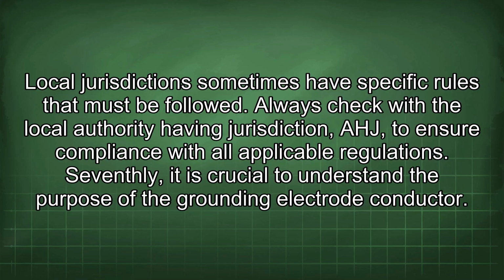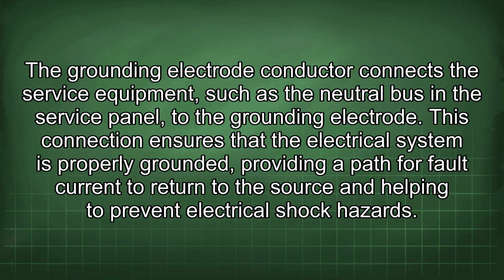Seventhly, it is crucial to understand the purpose of the grounding electrode conductor. The grounding electrode conductor connects the service equipment, such as the neutral bus in the service panel, to the grounding electrode. This connection ensures that the electrical system is properly grounded, providing a path for fault current to return to the source and helping to prevent electrical shock hazards.